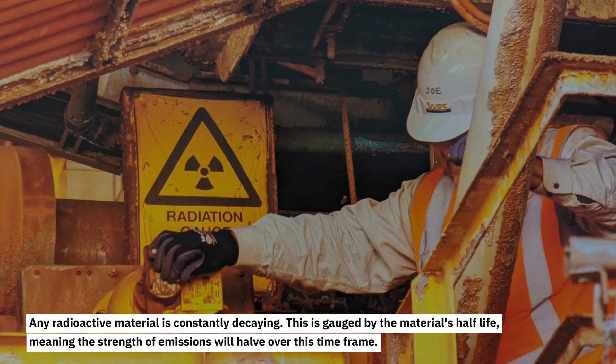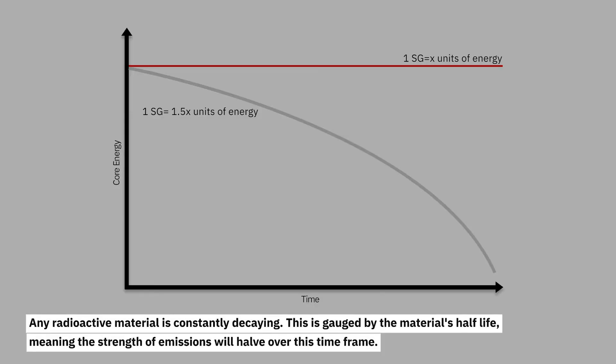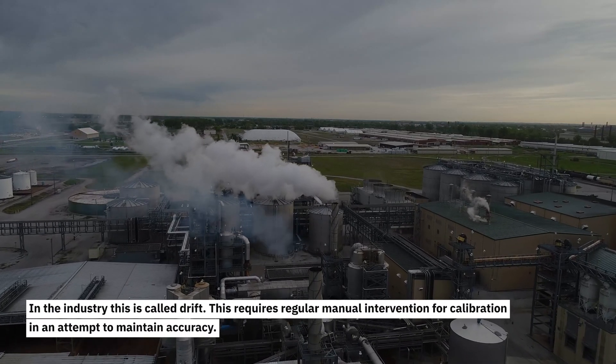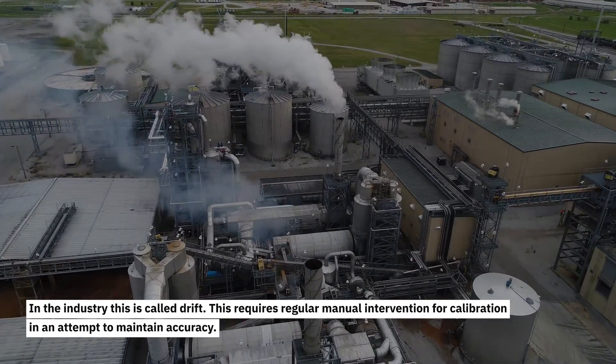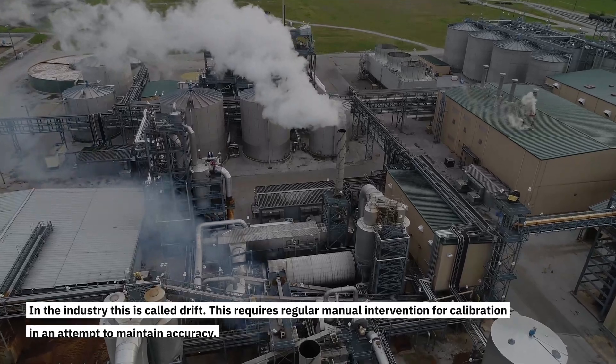Any radioactive material is constantly decaying. This is gauged by the material's half-life, meaning the strength of the emissions will halve over this timeframe. In the industry, this is called drift. This requires regular manual intervention for calibration and an attempt to maintain accuracy.